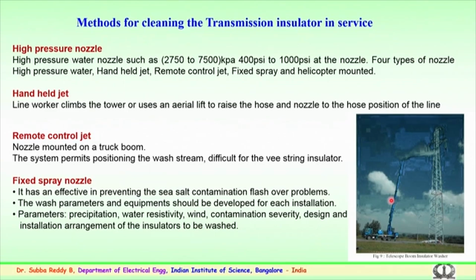So, the utilities watch the parameters, and the equipment should be suitably developed and used. It is not that the parameters are commonly kept the same, similar to other conditions of the environment. The parameters could be like the precipitation, water resistivity, so how much is the conductivity or resistivity of the water, and the wind, the contaminant severity of that location, and the design and installation arrangements of the insulators to be washed. So, several of these parameters come in the way of designing the fixed spray system for cleaning the insulator. Sometimes, if the parameters are not properly tuned, there could be wear damage to the insulator petticoats or insulator shells. So, it is a very important aspect to tune the parameters to the required location of the insulators, with the required pressure, and the nozzle arrangements have to be done.